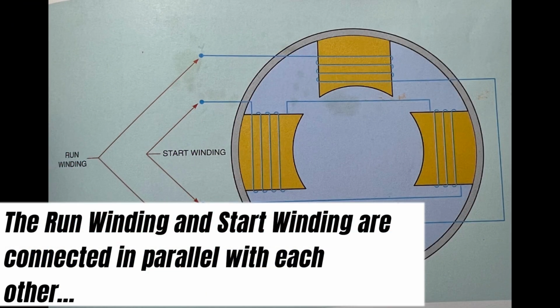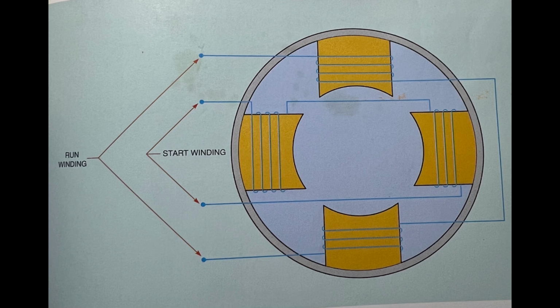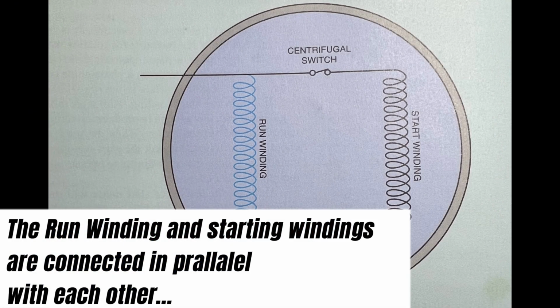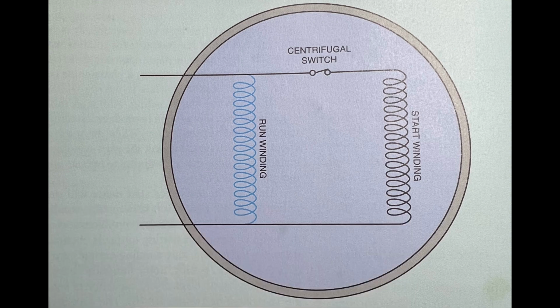The run winding is made of a larger wire and is placed deeper in the slots of the core material. The start winding is made with a smaller wire and placed near the top of the slots in the core material. The run winding, therefore, has less resistance and more inductance than the start winding. When the motor is started, these two windings are connected in parallel. Since the run winding has more inductive reactance and less resistance than the start winding, the current flow through the run winding lags the voltage more than the current flow through the start winding, producing an out-of-phase condition for these two currents. It is this out-of-phase condition that produces the rotating magnetic field.